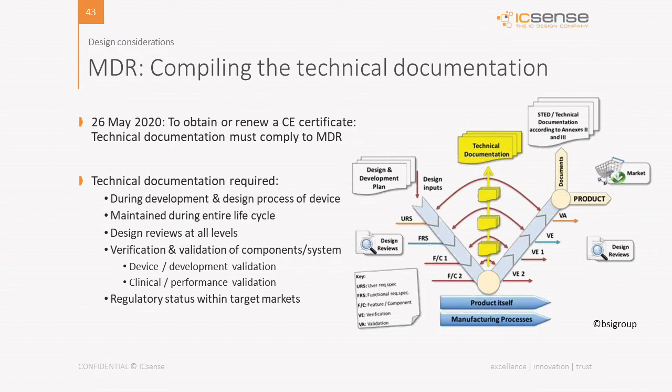What does this MDR require? It requires that all technical documentation developed during the design and development process of a device must be kept in records and maintained throughout its entire life cycle. That means the development and design process, but also the findings during verification and validation, even at clinical and market trials, must be kept on record.